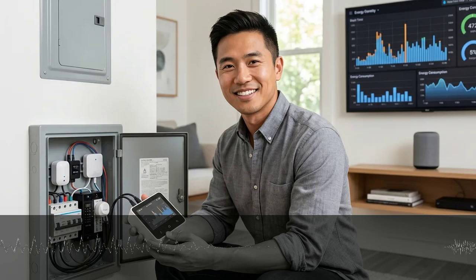You'll clamp CT sensors around your main power feeds, typically two 120-volt legs for split-phase 240-volt service in North America. You can optionally clamp individual CTs on specific breakers you want to monitor separately, then connect the monitor to Wi-Fi and configure everything through the manufacturer's app.